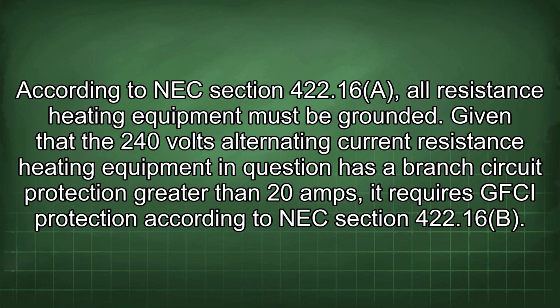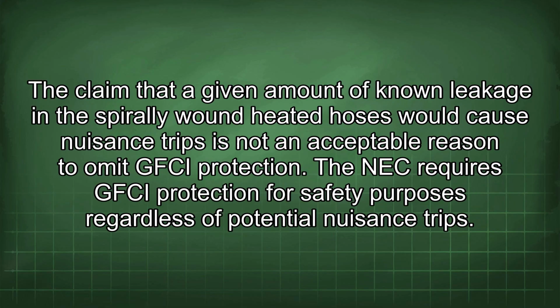According to NEC Section 422.16(a), all resistance heating equipment must be grounded. Given that the 240 volts alternating current resistance heating equipment in question has a branch circuit protection greater than 20 amps, it requires GFCI protection according to NEC Section 422.16(b).